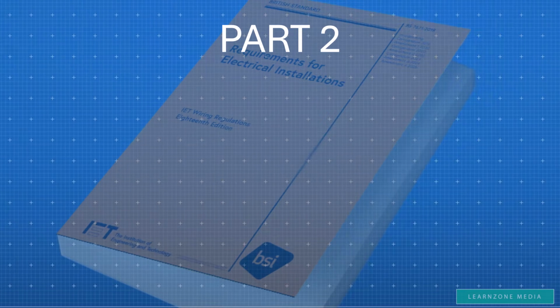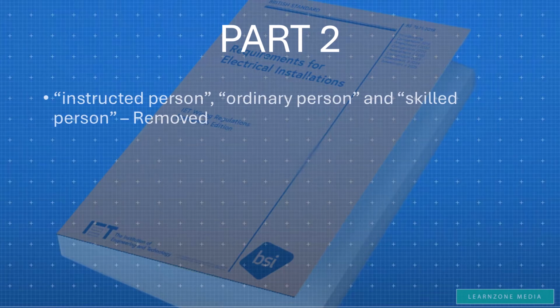Part 2, significant change to the terminology used. Instructed person electrically, ordinary person and skilled person removed from the definitions. The regulations now go back to the good old competent and experienced terms. The term isolator is now removed. Instead, the regulations now use terminology such as isolating device or disconnector. This will apparently aid clarity.